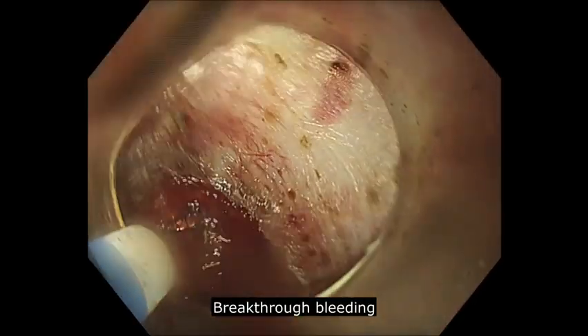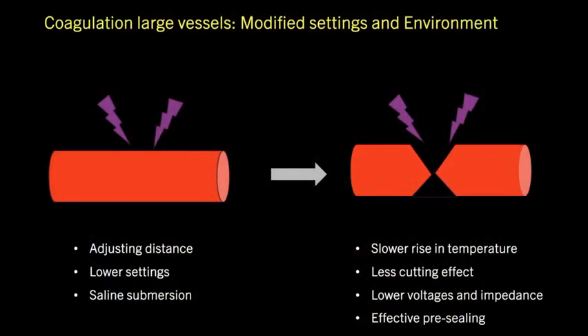For effective coagulation, the environment can be modified by adjusting the distance, lowering the settings, or submerging the target blood vessels under saline. This results in slower rise in temperature and less cutting effect due to lower voltages and impedance. This results in effective pre-sealing of large blood vessels.